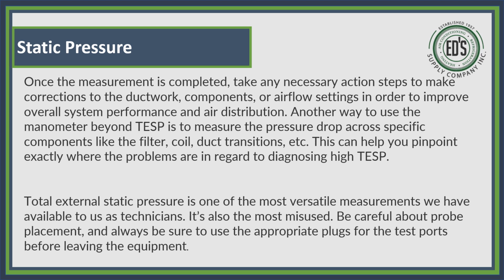Once the measurement is completed, take any necessary action steps to make corrections to the ductwork, components, or airflow settings in order to improve overall system performance and air distribution. Another way to use the manometer beyond the total external static pressure is to measure the pressure drop across specific components like the filter, the coil, duct transitions, etc., and you can actually pinpoint exactly where the problems are when diagnosing high static pressure. Total external static pressure is one of the most versatile measurements that we have available to us as technicians. It's also the most misused. Be careful about probe placement and always be sure to use the appropriate plugs for the test ports before leaving the equipment. Put a piece of mastic tape if you don't have the plugs.